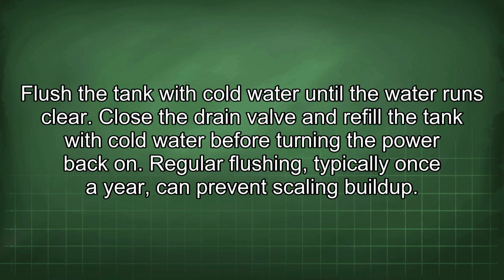Flush the tank with cold water until the water runs clear. Close the drain valve and refill the tank with cold water before turning the power back on. Regular flushing, typically once a year, can prevent scaling buildup.